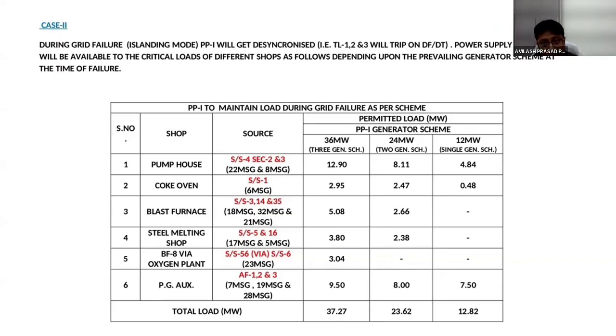If we are running on the 2 generator scheme, that is, we are generating 24 megawatt through our captive power plant, then we will give 8.11 megawatt to power pump house, 2.47 megawatt to our coke oven, 2.66 megawatt to blast furnace, 2.38 megawatt to steel melting shop. We will cut the power to oxygen plant and we will give 8 megawatt power to PG auxiliary units.